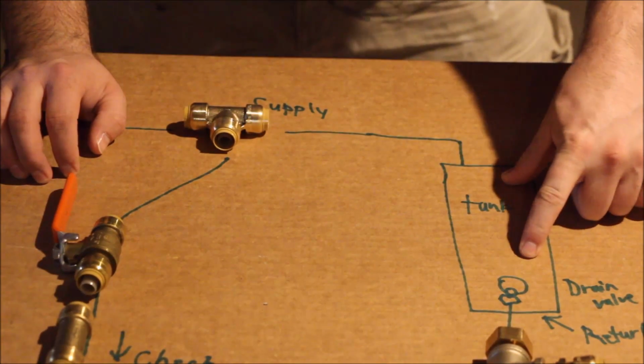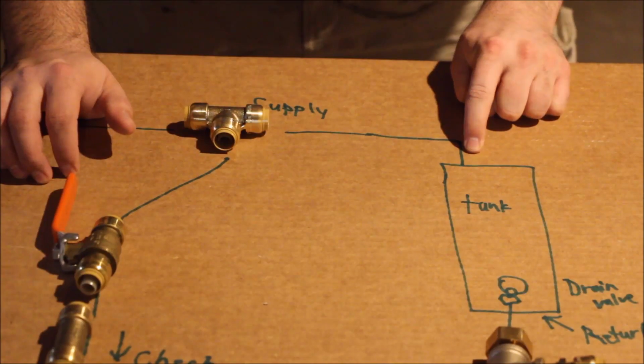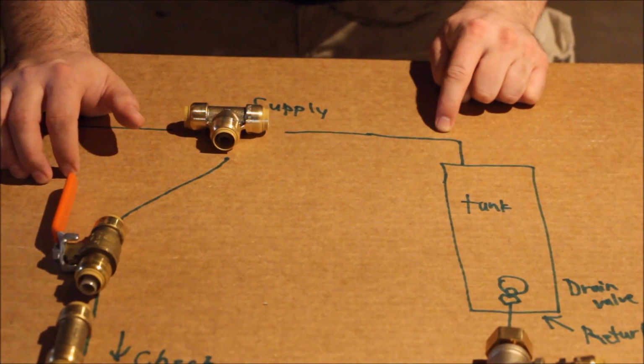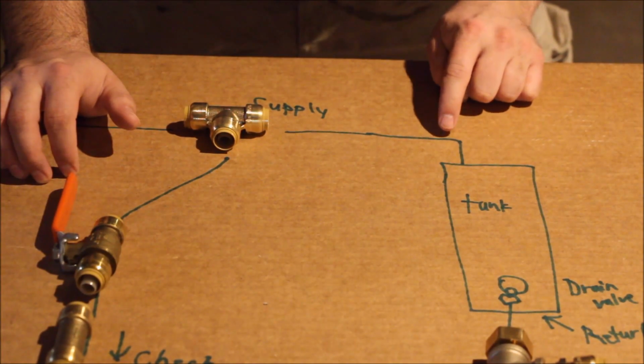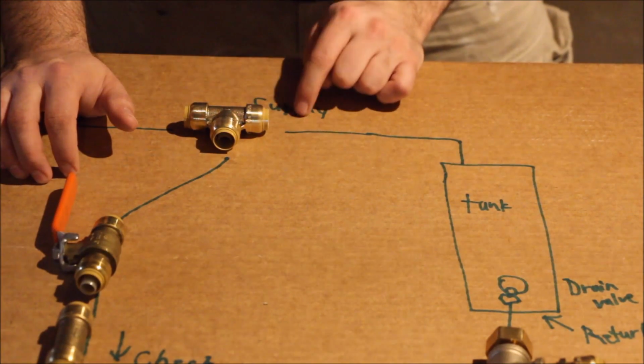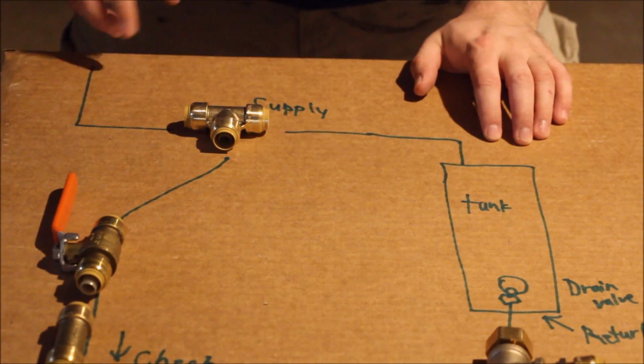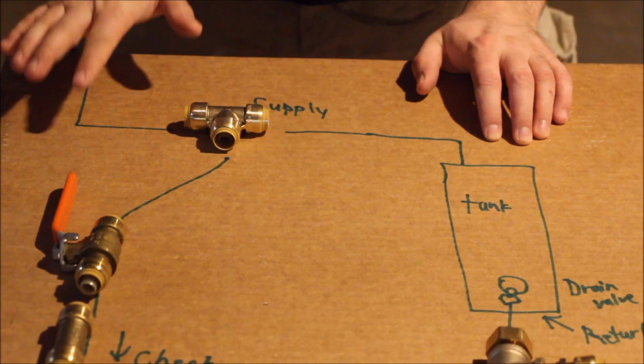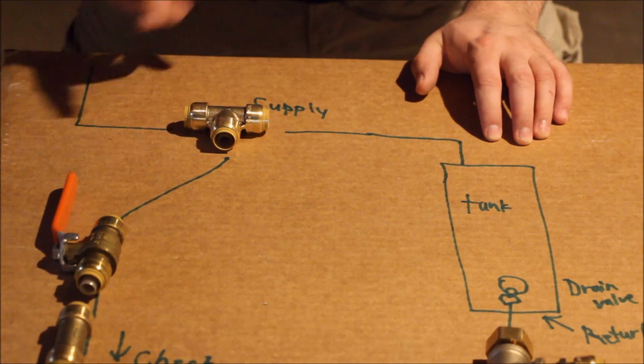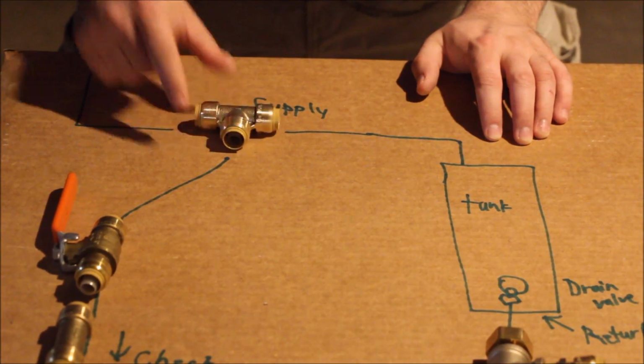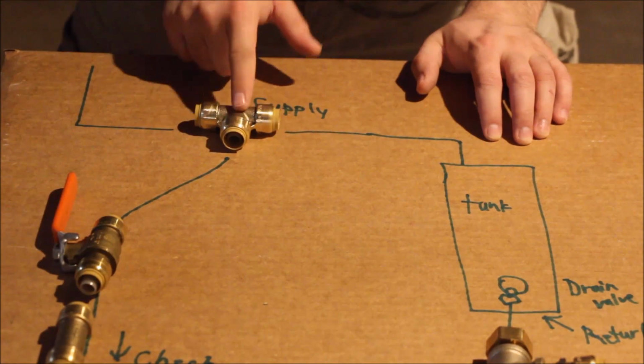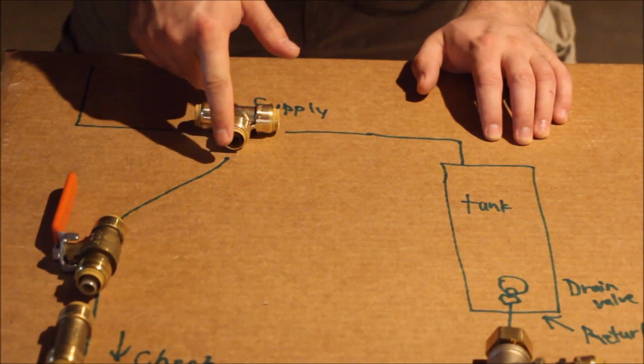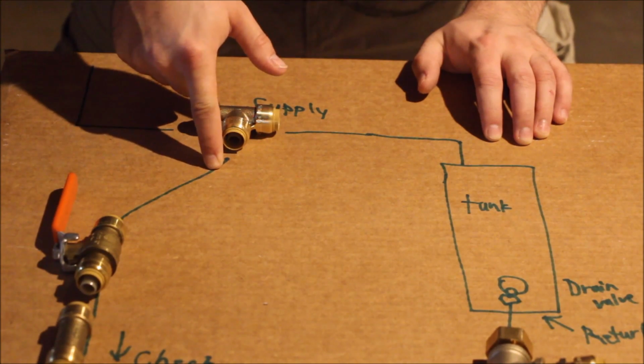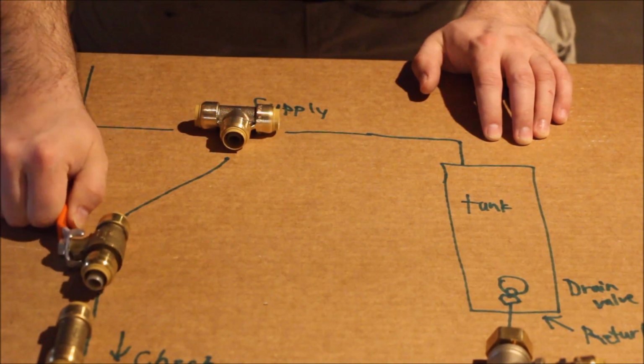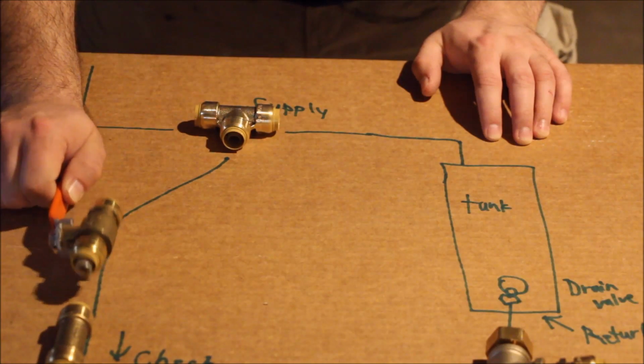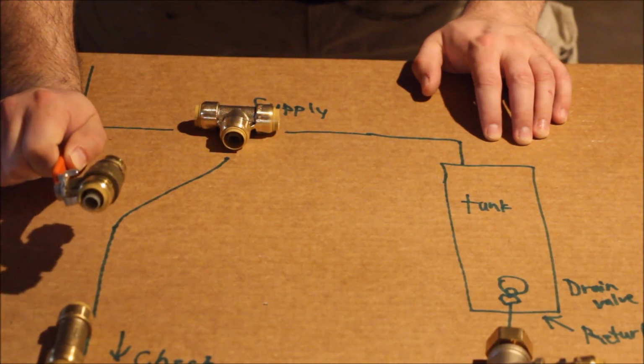You have your hot water tank, and out of the top you're going to have supply lines running out. I have a supply line going to my washing machine. I don't want to interrupt it and stop it from going there, but I'm going to cut into it, break into it, and put a T-fitting in, then tap off that T-fitting and go to a shut-off valve. This will allow me to control the supply line for my heat pump.